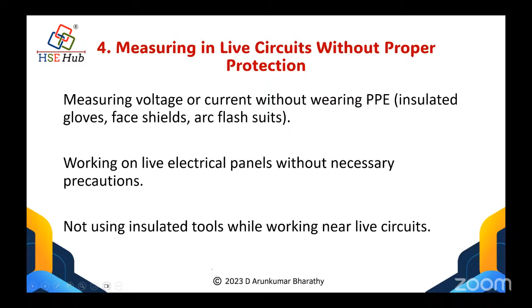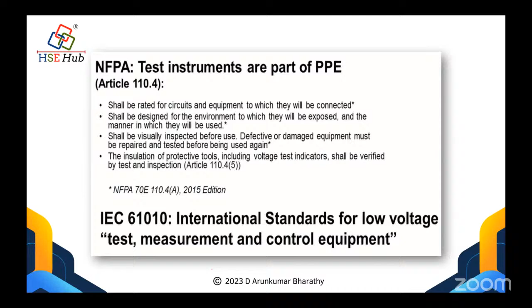Okay. Yeah, this is the standard: NFPA 70E Article 110.4 says that test and measuring equipment, also a part of PPE, shall be rated for the circuit and equipment. If we look below, there is a standard IEC 61010, that is the international standard for low voltage test, measurement and control equipment. In this webinar, we are focusing only on handheld test and measuring equipment. This standard is now updated, 61010 parts 3 and 4. Now they are upgraded and have incorporated a lot of technologies in these standards so that any instrument available globally will meet all the safety standards, right?